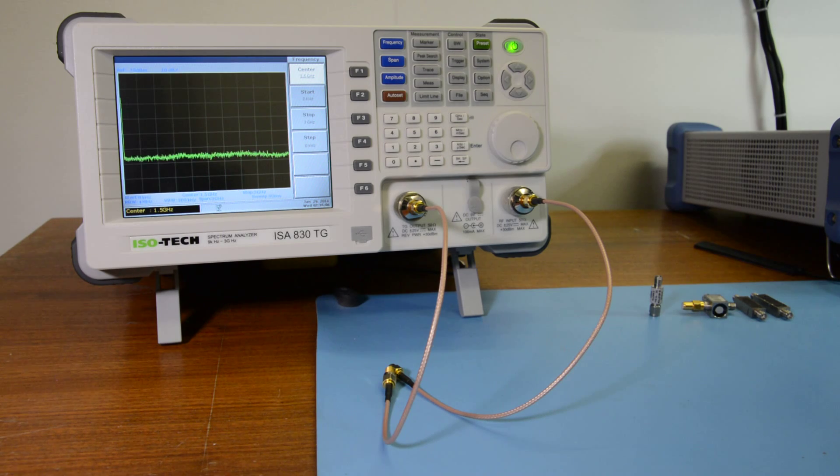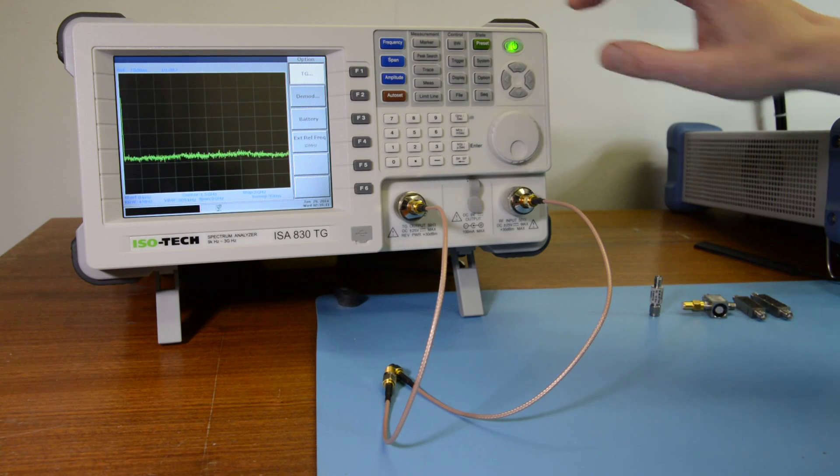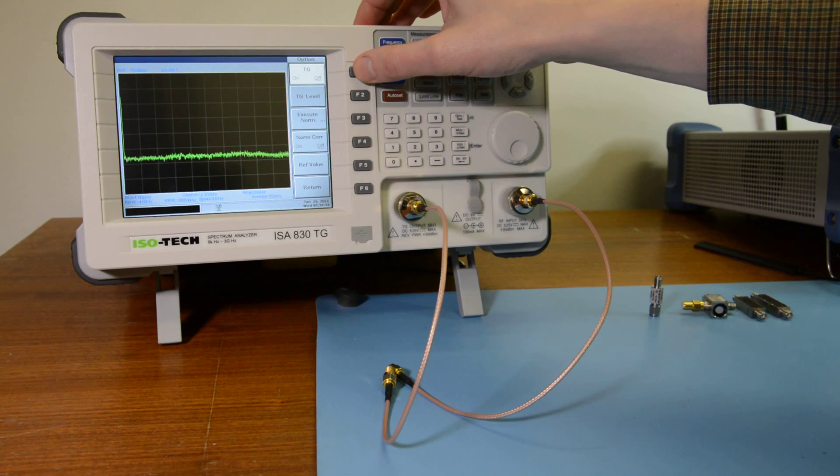Now to enable the tracking generator we need to press the option key, followed by F1 TG, and then F1 again to turn the tracking generator on.